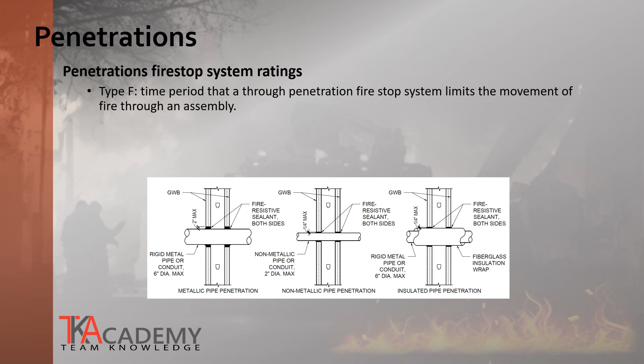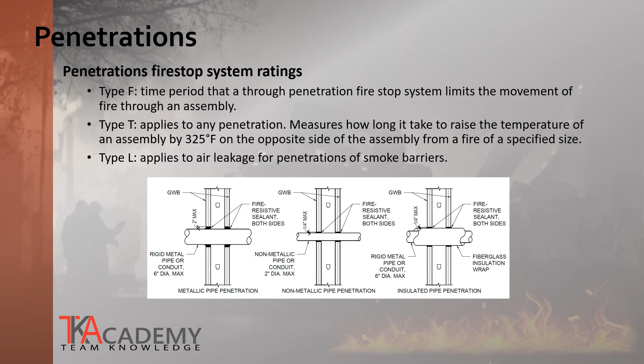A Type F rating means a time period that a through penetration fire stop system limits the movement of fire through an assembly. A Type T rating applies to any penetration, and it measures how long it will take to raise the temperature of an assembly by 325 degrees Fahrenheit on the opposite side of that assembly. A Type L rating applies to air leakage for penetrations of smoke barriers.